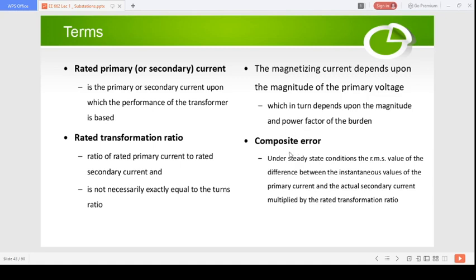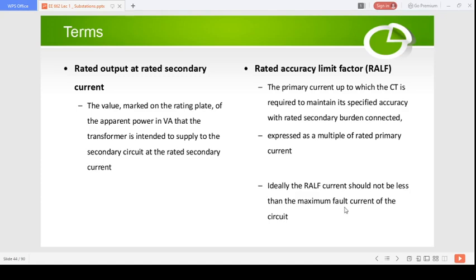There's another term called the composite error. The composite error is defined, under steady state conditions, as the RMS value of the difference between the instantaneous value of the primary current and the actual secondary current multiplied by the rated transformation ratio.